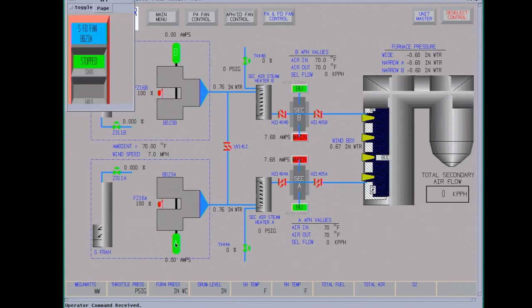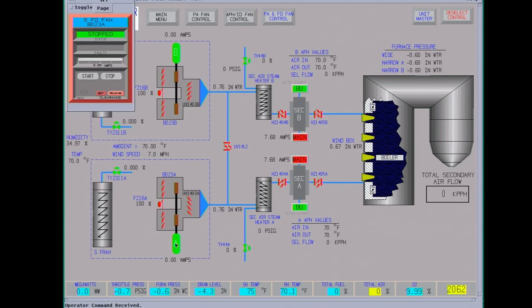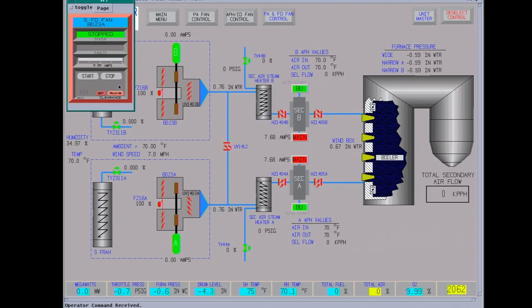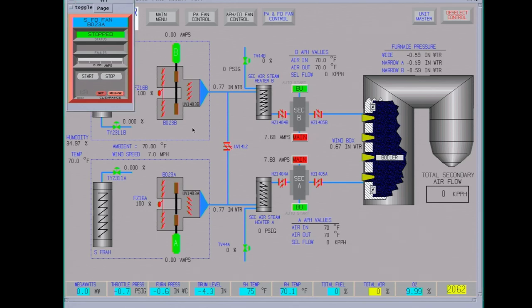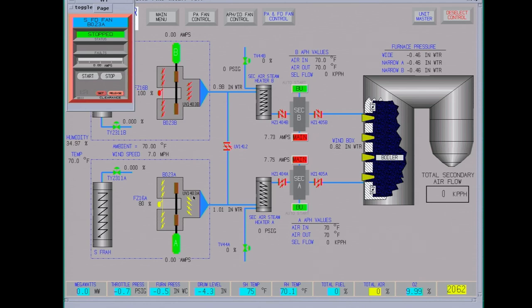We're going to start the A motor. That's around 2,000 horsepower motor. These kind of motors, you got three starts per hour. There's a lot of rules as to how often you can start them. As you can see, the dampers are driving closed. Once these are closed, then the motor will start. You also want to watch the amps.